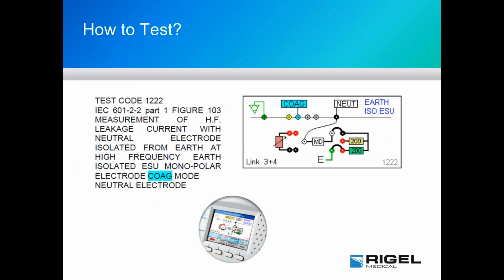So now with the Uni-Therm, and that's one of the test screens on the right center and lower center of the display. And I guess one thing that I should comment on here is when you look at these test screens, when we're doing power testing with the Uni-Therm, we allow you as the biomed to select whether you want to look at a test screen or not. When you're doing high frequency leakage testing, every test screen is slightly different than the one preceding it. So we kind of do force you looking at a display to make your connections. When we talk about our auto test sequences, we have the right connection diagrams implemented in the test procedure for what you're trying to do.